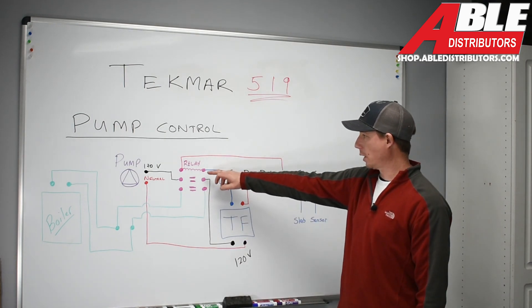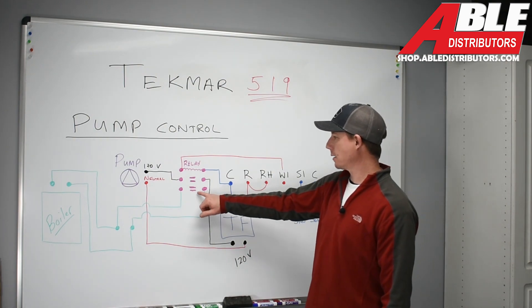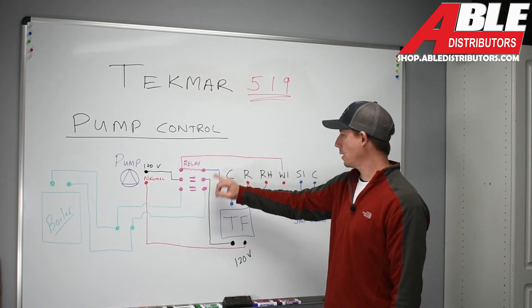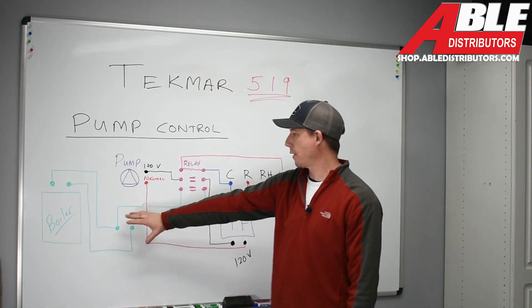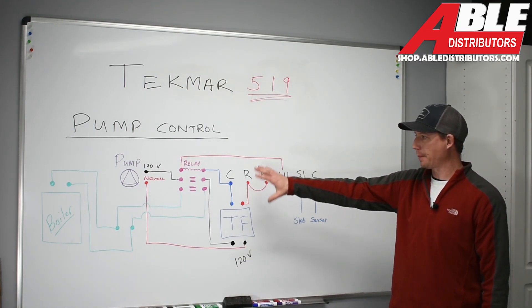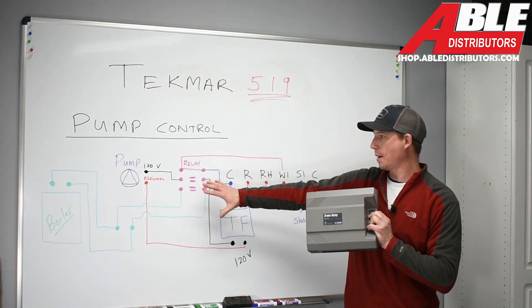When that relay closes, it engages 120 volts to the pump, and the neutral comes back down to complete that circuit — the pump is up and running. On the second set of contacts on this relay, we have our boiler circuit. When W1 energizes the relay and we complete the circuit back to common, that second set of contacts closes and fires the boiler up. Both operations happen simultaneously once the relay is energized. For those where this seems complicated, Able Distributors provides a simple solution — the Caleffi zone panel relay — which incorporates this whole wiring diagram into a simple solution.